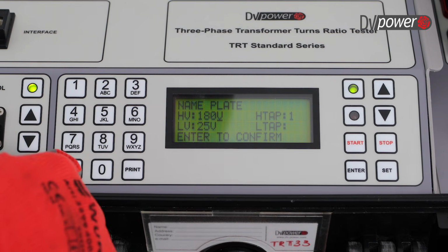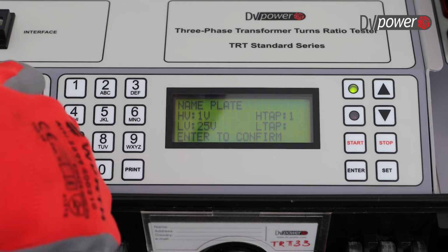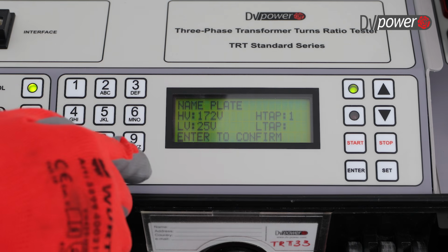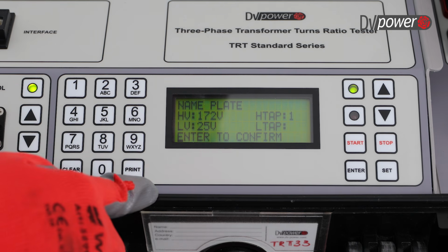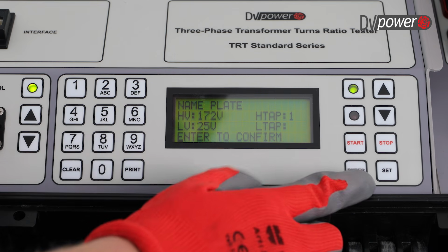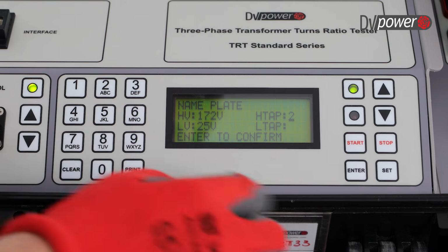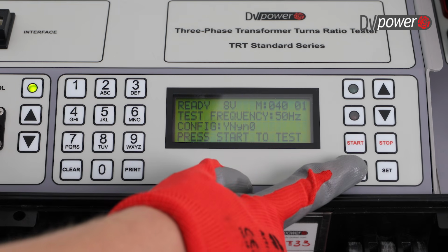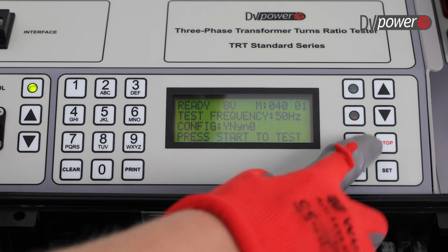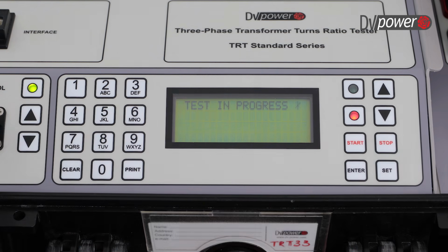So we need to change the nameplate for this position. It is 172 volts to 25 volts. It's the second tap position. Press enter to confirm. Double check it and press start. And we have our results.